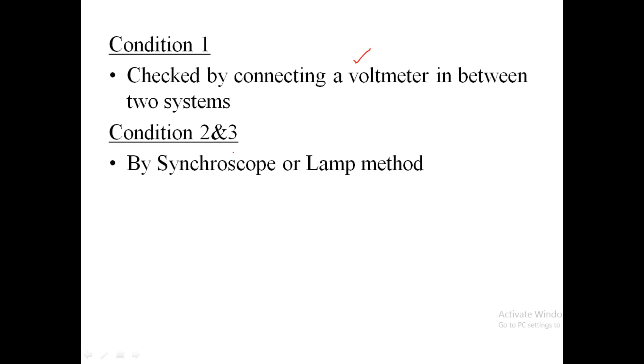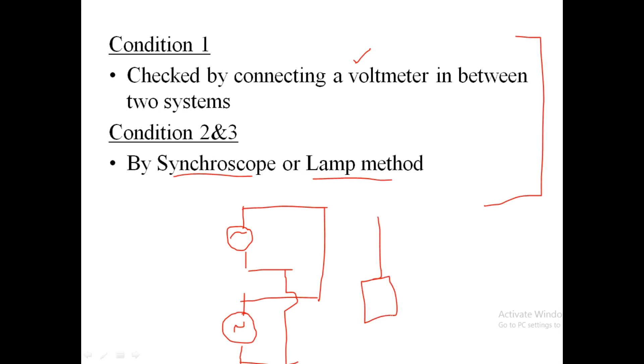So if these conditions are not satisfied, what will happen? There will be a circulating current in between the systems. That means here we are having a generator, here we are having another generator. Both the generators are supplying load, and these are connected in parallel. So how the current should flow in this system? Current should flow to the load only, from both the generators, current should flow to the load.